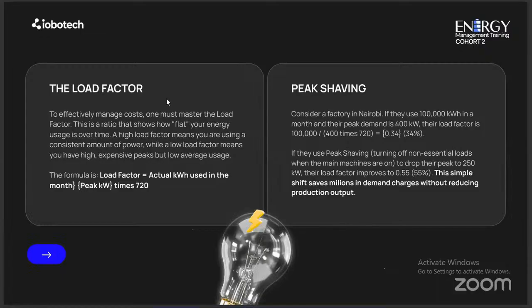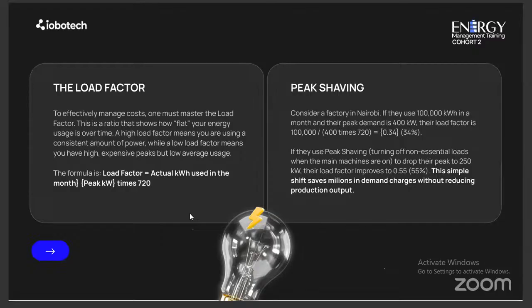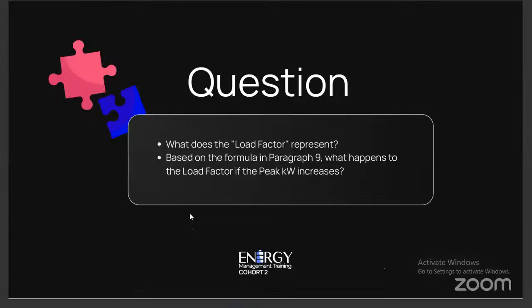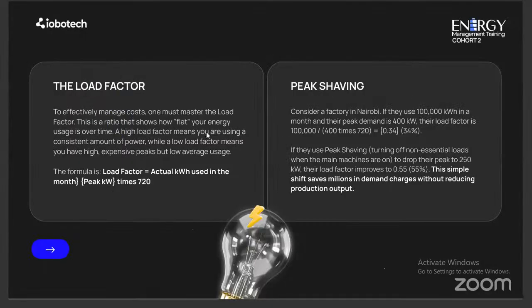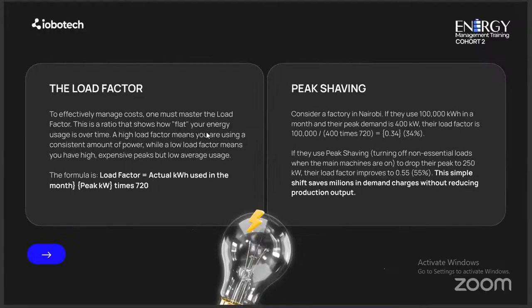And relating to energy management, the goal of the energy manager is always to maintain a very high load factor. A high load factor represents good, consistent usage that does not involve high peaks with low average usage through the month. When the peak kilowatt increases, the formula gives you a lower load factor. So you're going to try to minimize the peaks as much as possible.